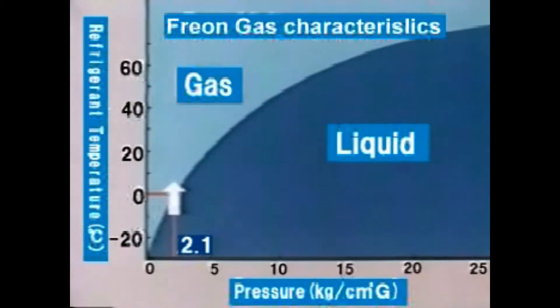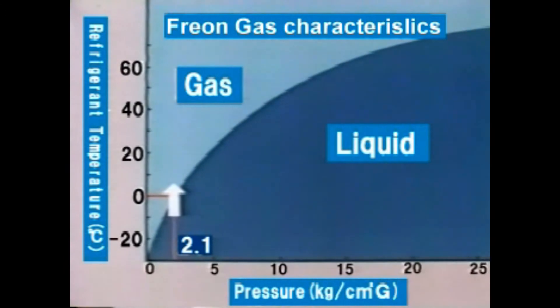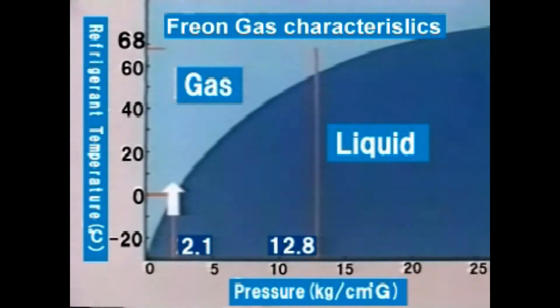Refrigerant expanded by valve now stays in the form of vapor at pressure 2.1 kilograms per square centimeter and zero degrees centigrade. It will be gasified when heat is taken by the evaporator. Meanwhile, the compressed refrigerant exists as a gas at a pressure of 12.8 kilograms per square centimeter, 68 degrees centigrade. When its heat is released by the condenser, it is liquefied.